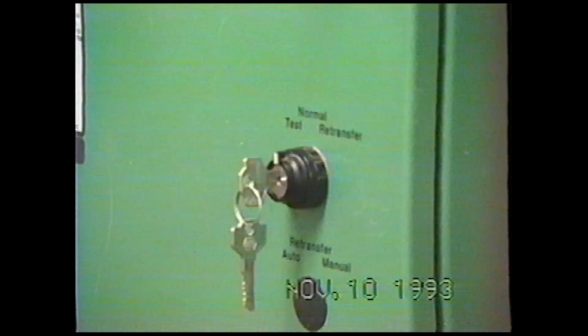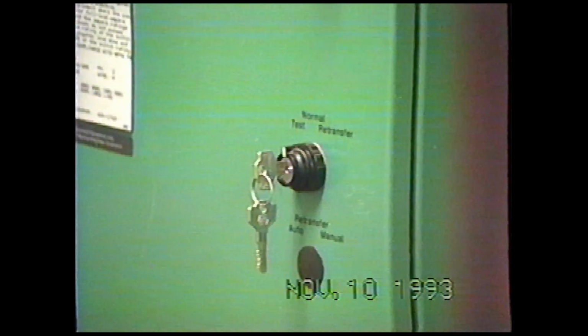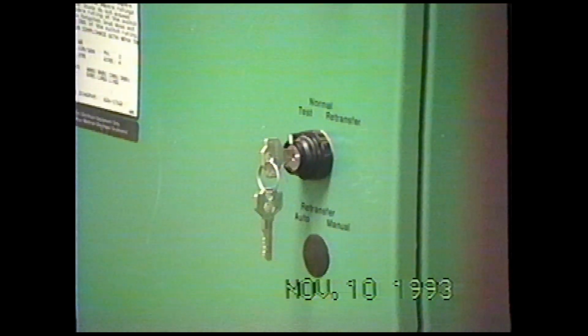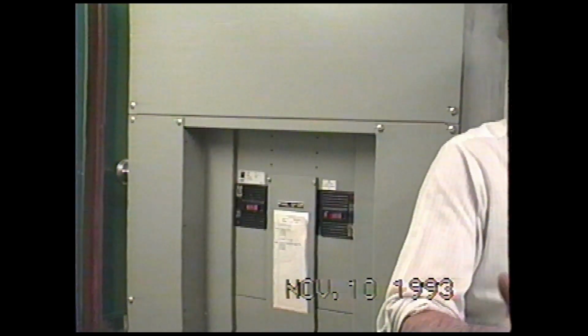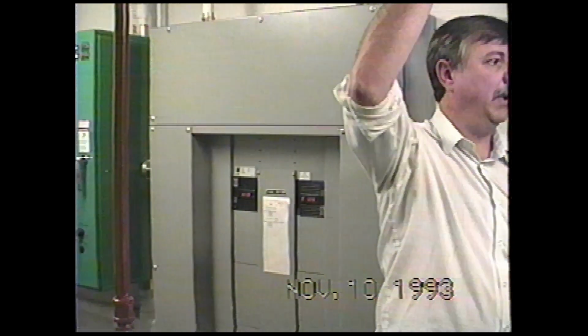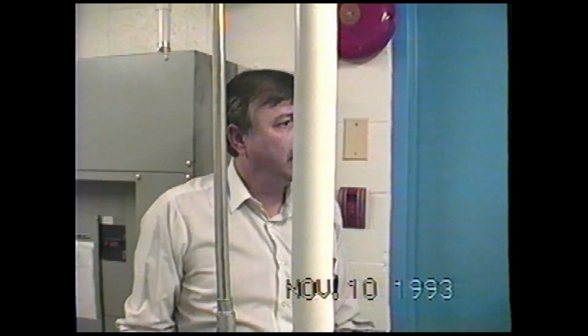Talking to Tom, when we start this up for load shedding, even if the load drops down and it says it doesn't need to load shed anymore, we keep it running for 3 hours. He asked for that, 3 hours, it's a long time. He said in the summertime, which is probably when load shedding takes place, we don't want to be shutting the generator off and watching the load come back up and then starting it again. If you're in that borderline situation, it just comes on and runs 3 hours.